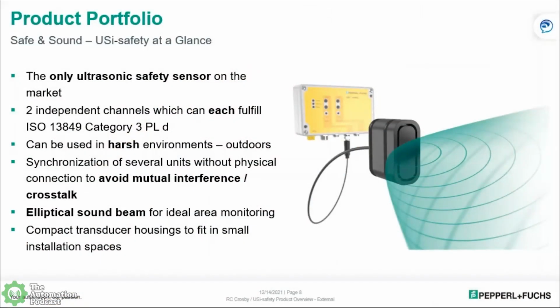Yeah, it looks like it's about the size of a matchbox. From what I'm seeing, it is very small. They come in two lengths. The transducer cables come in two lengths, either 1.5 meters or, as I have here, 3 meters. So great for size restrictions. The evaluation unit gives you two independent, redundant channels. They each fulfill ISO 13849 up to a category 3 performance level D with proper installation and wiring methods.